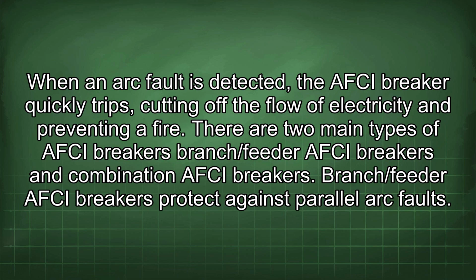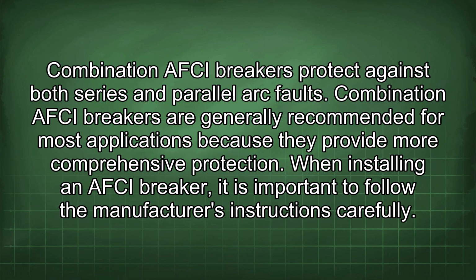When an arc fault is detected, the AFCI breaker quickly trips, cutting off the flow of electricity and preventing a fire. There are two main types of AFCI breakers: branch/feeder AFCI breakers and combination AFCI breakers. Branch/feeder AFCI breakers protect against parallel arc faults. Combination AFCI breakers protect against both series and parallel arc faults. Combination AFCI breakers are generally recommended for most applications because they provide more comprehensive protection.